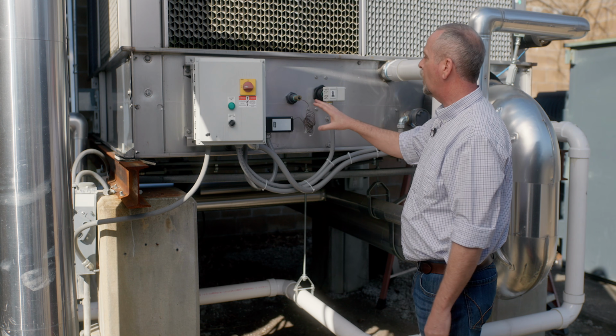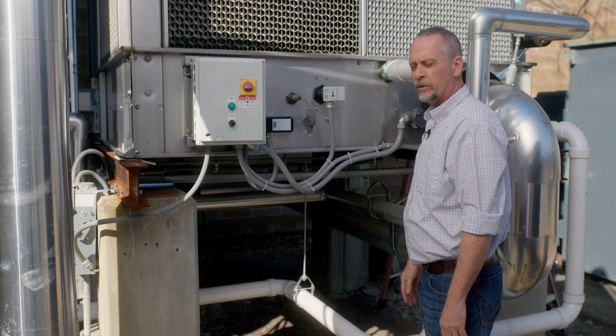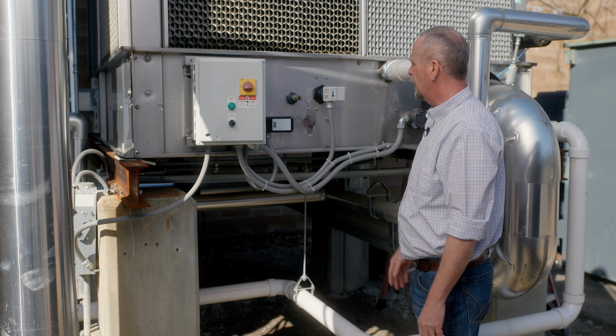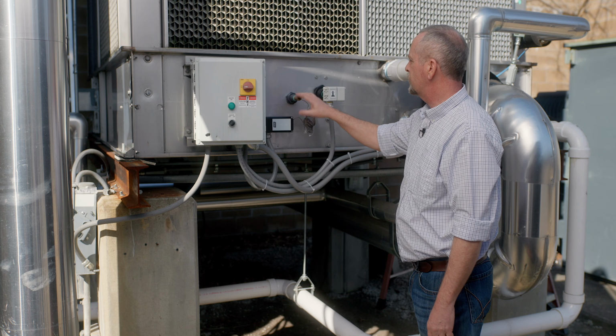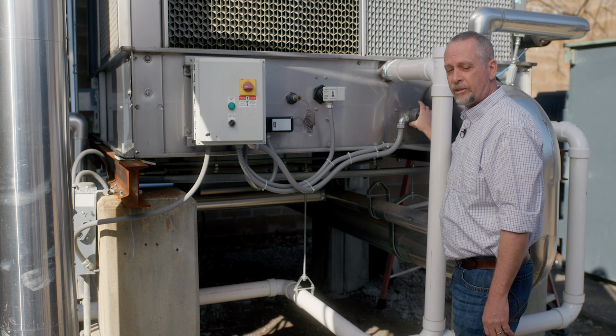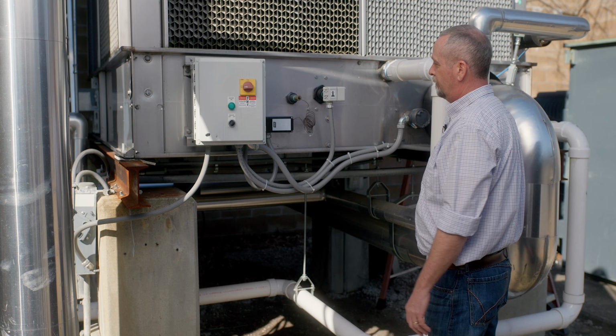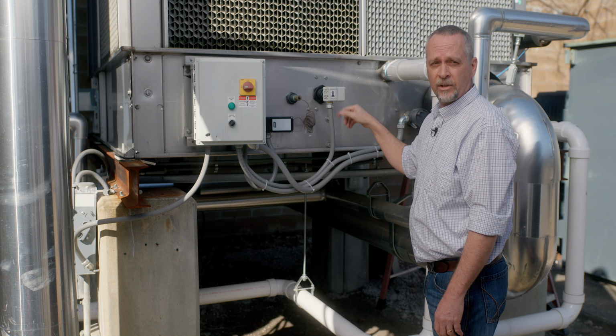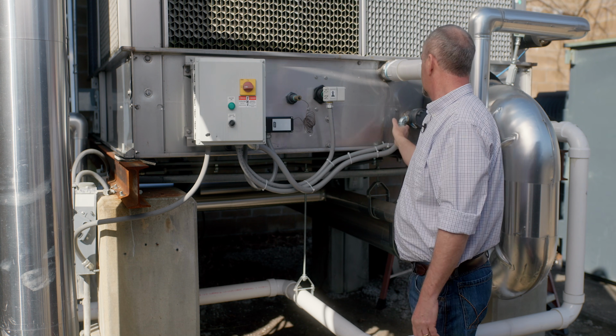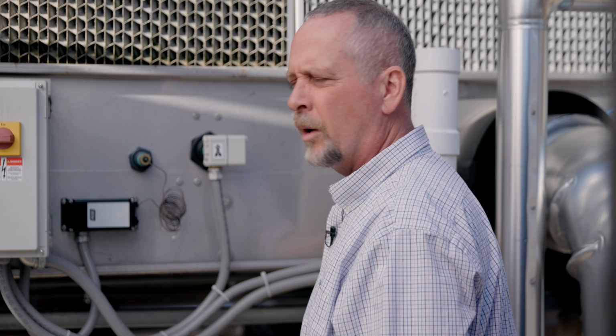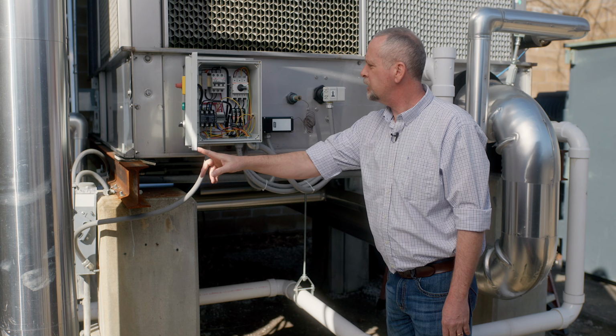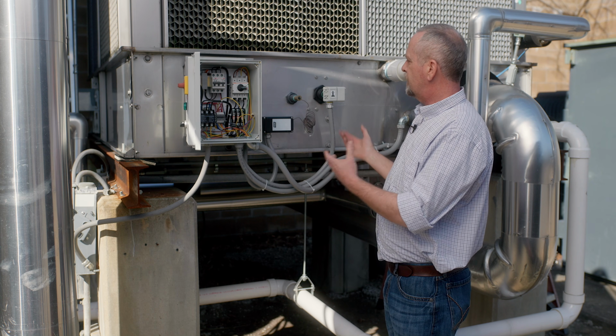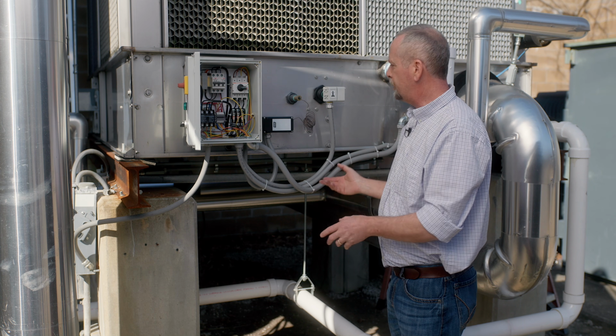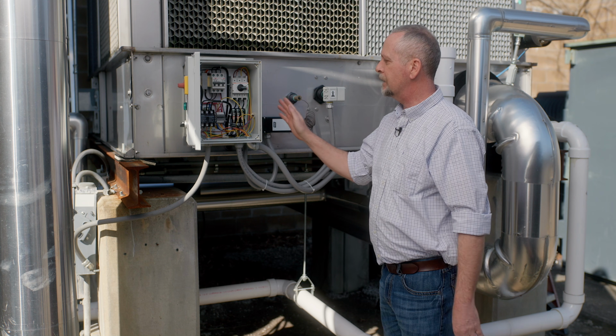So it's very important to also check these devices when you're doing your annual maintenance on these towers. Make sure these components are functioning right. If you come across one and your heater's busted, I'm definitely checking these first to make sure I don't have a problem there, because again, that heater should always be underwater protected. Everything else is pretty straightforward, but as simple as this may or may not sound to some people, it is critical and it gets missed a lot.